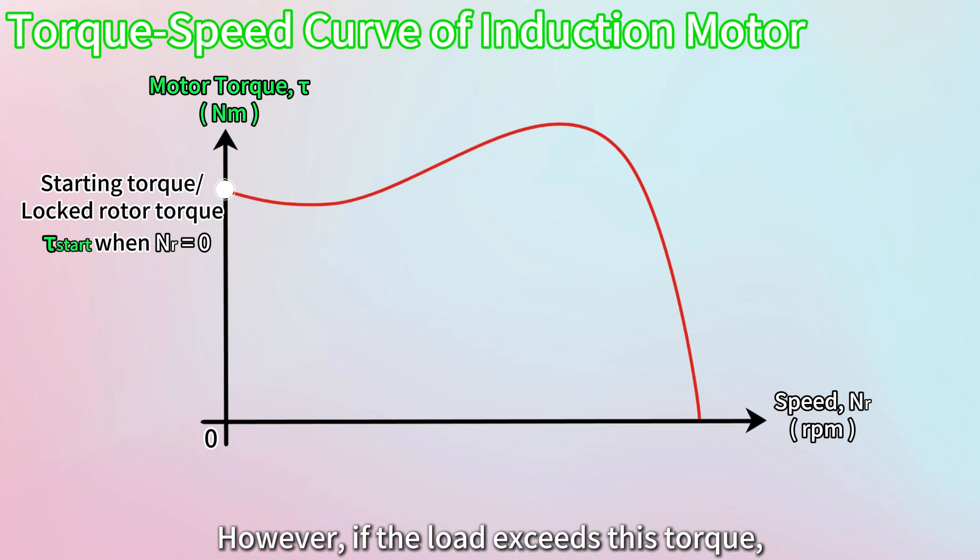However, if the load exceeds this torque, the motor will fail to start. Next, as the motor accelerates, there is a temporary dip in the available torque, and the lowest point during this acceleration phase is known as the pull-up torque.